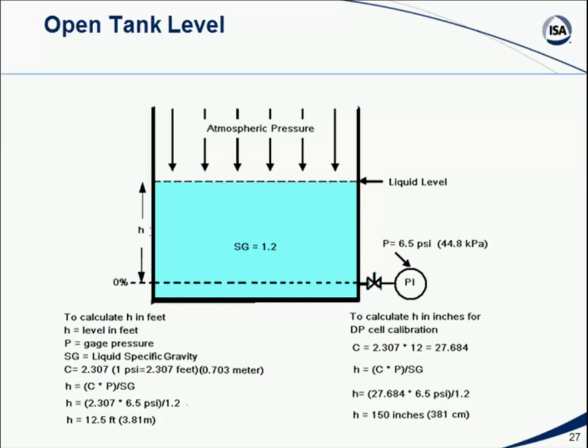And we're not showing the other side, but if you were to take that PI device and draw a pipe out from the right side and just let it hang in air, you'd have a much more realistic diagram here. So in fact, this PI device has one of its sides open to the atmosphere. Because it's open to the atmosphere, that side is feeling atmospheric pressure at 14.69 psi. So the pressure that it's feeling from its open tap on the right side is canceling out the pressure that the atmosphere is placing on the measurement it's taking on the left side, and therefore the only pressure we're really measuring is that which is in the tank. Okay, which is in the tank. So if we use differential pressure measurement and we open one side of the pressure measurement device to the atmosphere, then it will correct for the fact that the atmospheric pressure on the open tank is this 14.69 psi. So we've got to be able to correct for that.